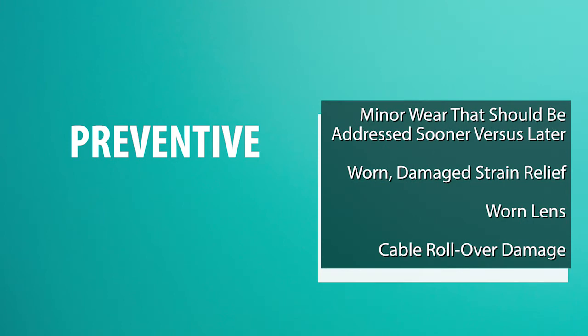Preventive indicates that issues have been identified with the probe that need to be addressed sooner versus later. The probe can be used in its current state, but performance and/or physical integrity will be compromised in the future. Examples are a worn or damaged strain relief, cable rollover damage, or lens wear.